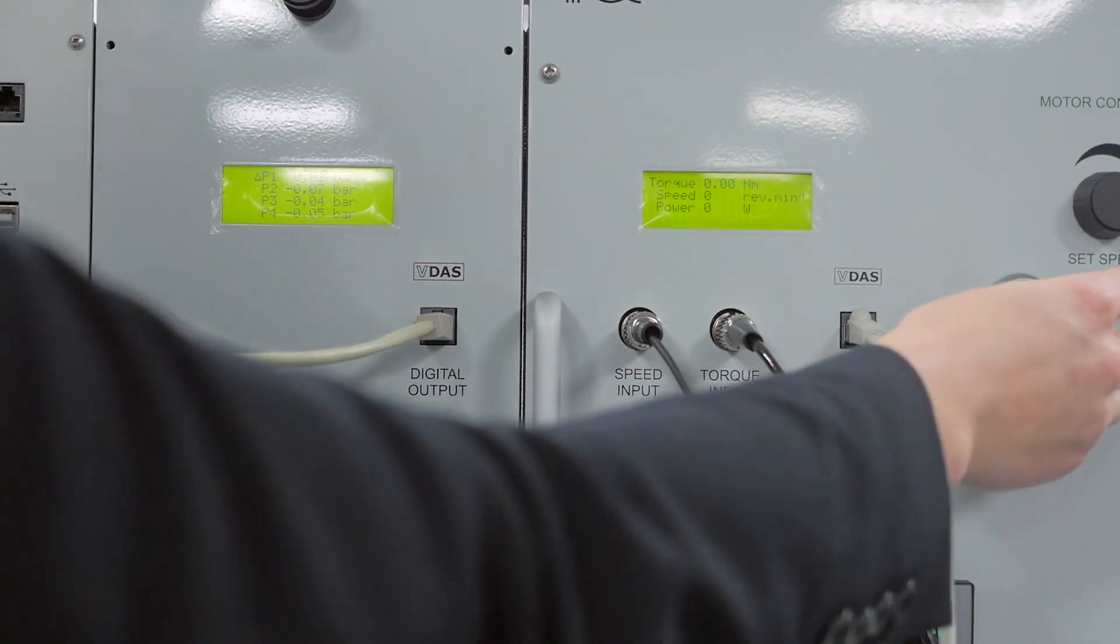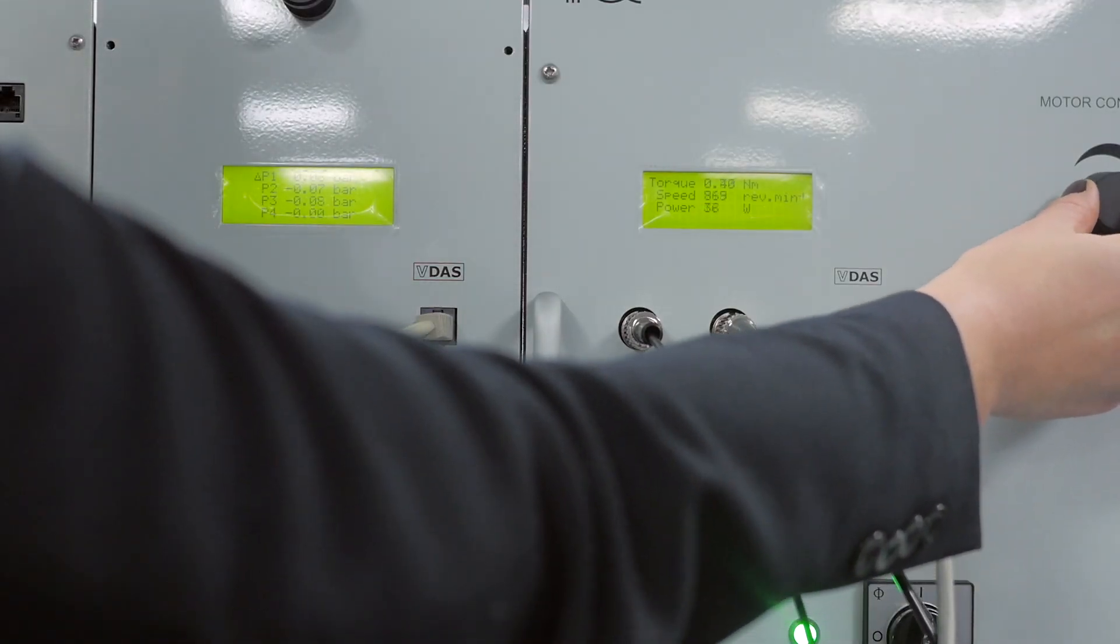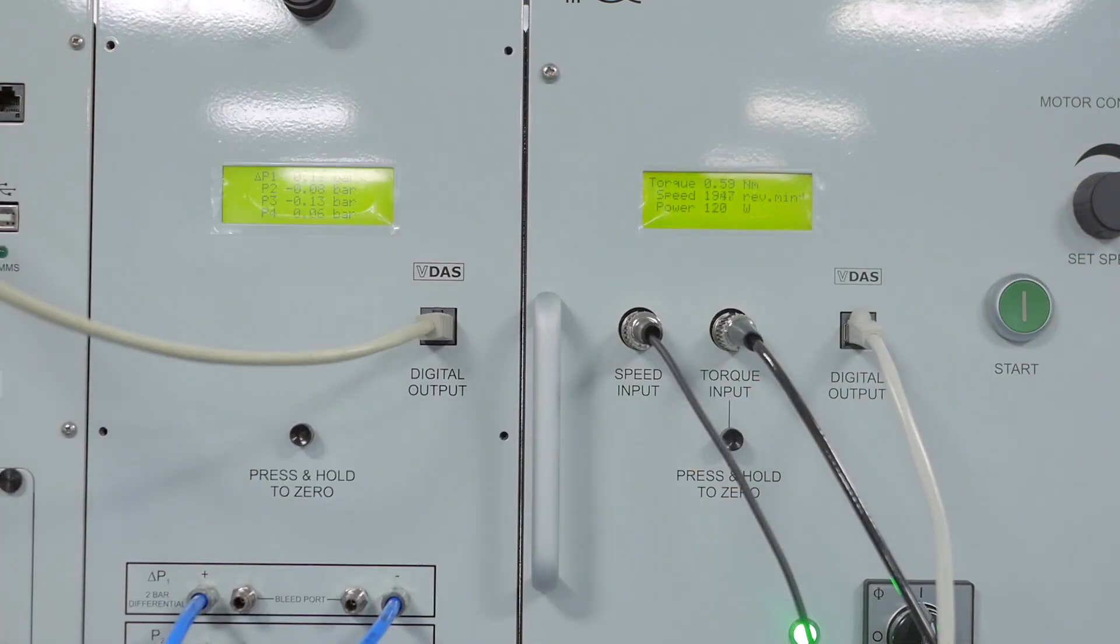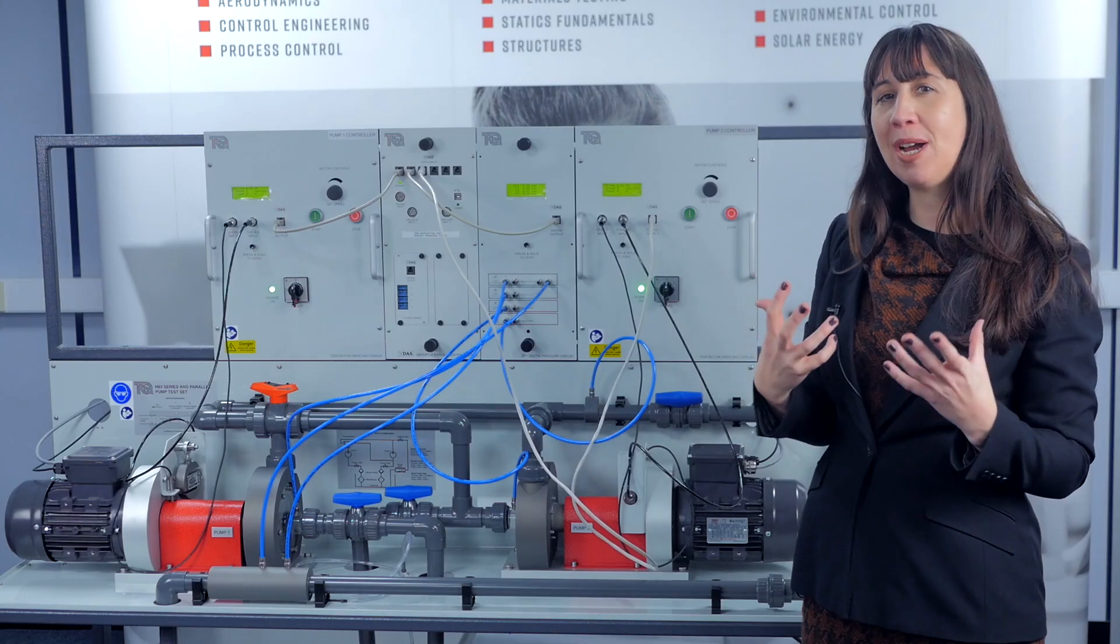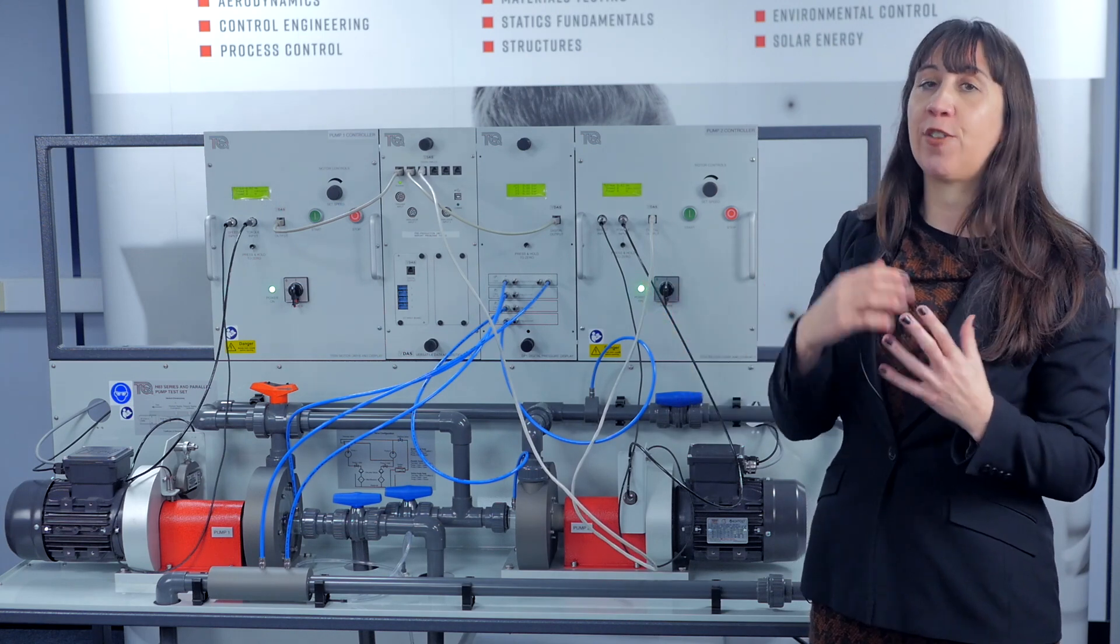A display for each motor drive shows speed and torque and automatically calculates and displays true shaft power. The differential pressure across the venturi gives flow rate.